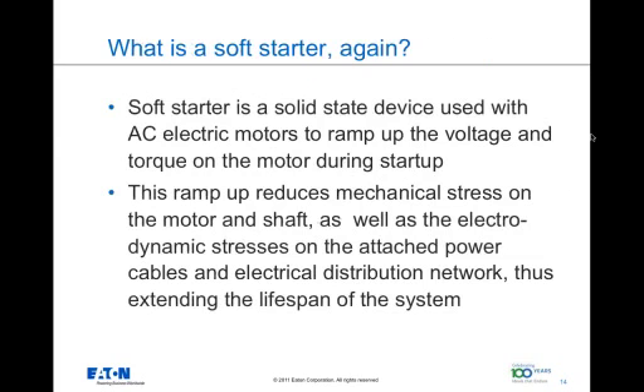Let us now revisit what a soft starter is, keeping the reduced voltage mechanisms that are out there in perspective. A solid-state soft starter is a solid-state device which gradually ramps up the voltage and, as a result, the torque associated with it. This gradual ramp-up significantly reduces the mechanical and electrodynamic stresses generated in the system. When these stresses are reduced, your system life increases and your maintenance cost decreases.